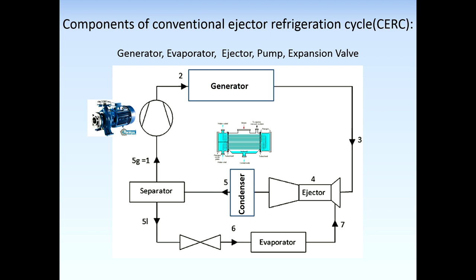Regarding the condenser, the heat of the vaporized refrigerant is exchanged with the condensation fluid, which is water or air. The expansion valve has two tasks: first, to flow the liquid refrigerant from the condenser to the evaporator at the same rate of evaporation, and second, to make a pressure difference between them so that both can work properly.